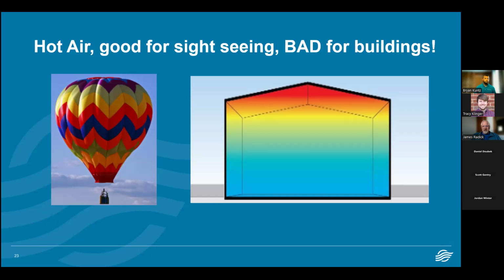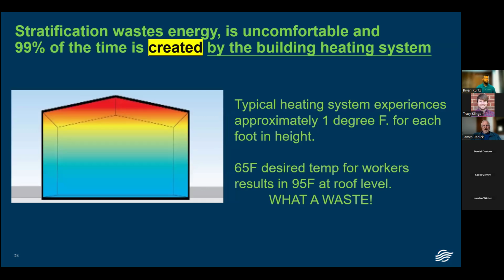In fact, if we go to the next slide, stratification wastes energy, it's uncomfortable, and 99% of the time it's created by the building heating system. Okay, that is a powerful thing to get our hands around. Typical heating systems that discharge high temperature air into the space, unit heaters, et cetera, whatever it is, can be expected, and this is well documented, to experience approximately 1 degree Fahrenheit rise for each foot in height as you get away from the floor.